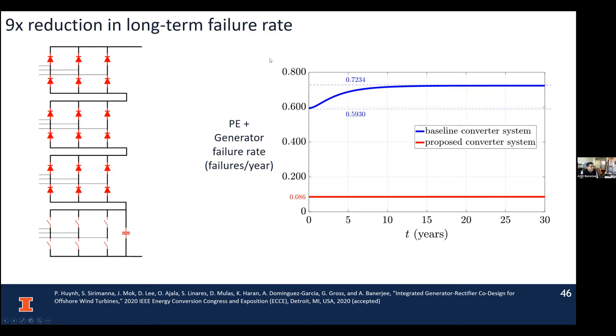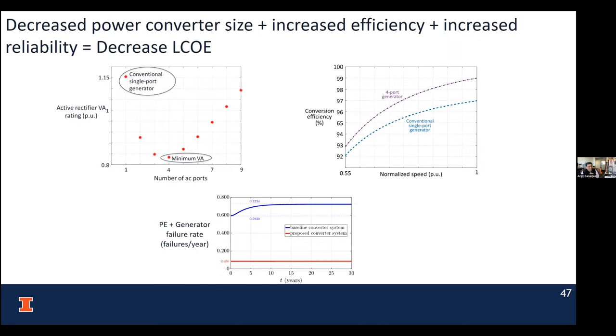The data shows that for the conventional architecture, you can see why reliability degrades over time -- this characteristic comes from the capacitance. Imagine you have a full DC bus capacitance; that's what gets reflected in this gradual increase in failures per year. Compared to the conventional baseline, the proposed architecture has a 9x order of improvement in reliability. So to summarize, we have better VA rating, better efficiency, and finally better reliability, and that's what drives us to decrease the LCOE.